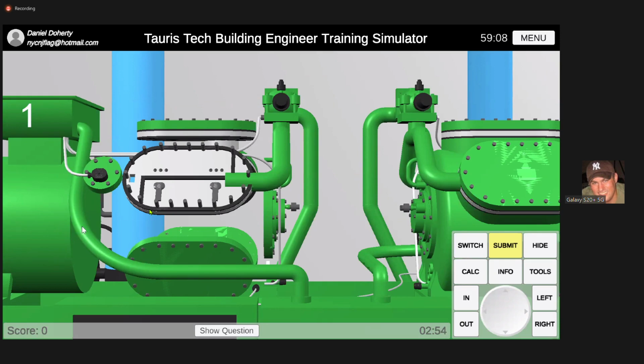Okay, so the vapor comes through the motor. It's still low pressure. And then you see this little hole here on your valve plate that I'm pointing to? Yeah. So the vapor comes in there. Now, you see the gasket around the valve plate? And you see how the gasket also goes across the middle like this? Okay? So the upper part of your gasket is the low side of the refrigeration cycle. So that low pressure vapor comes through the motor, it comes out this hole, and then it gets pulled in.